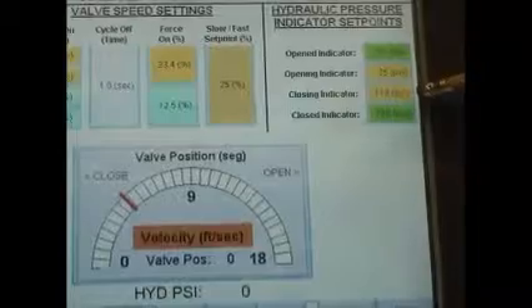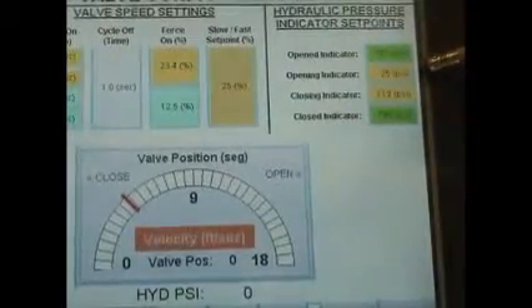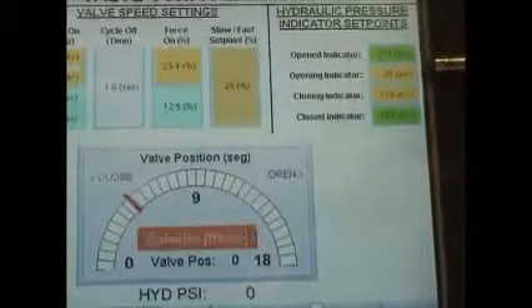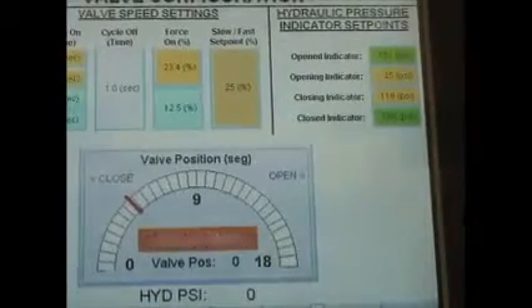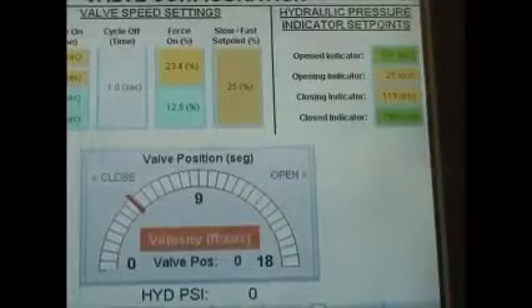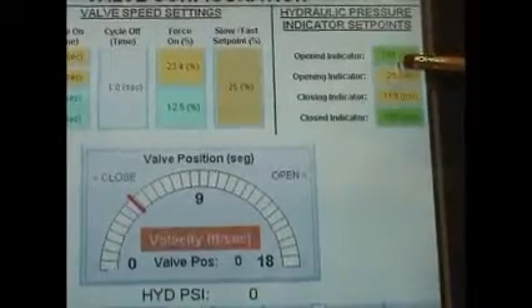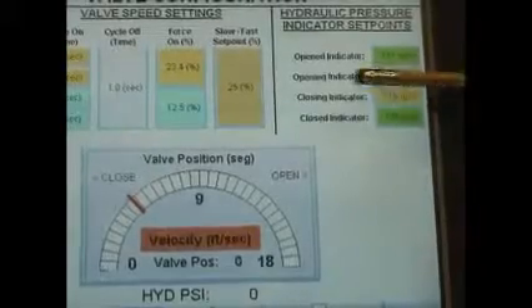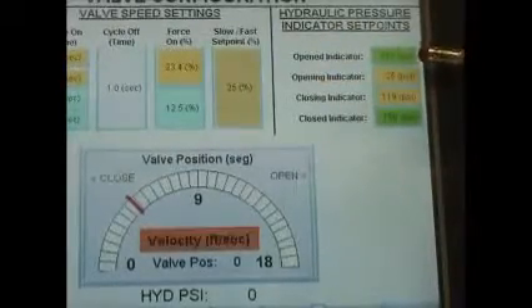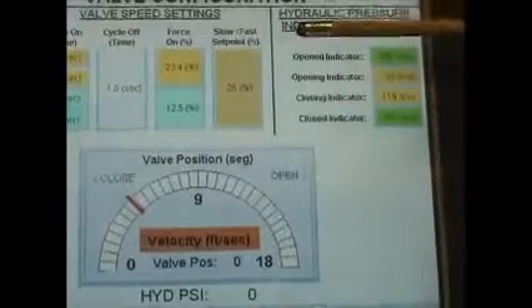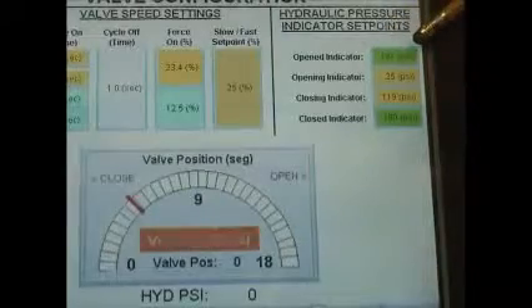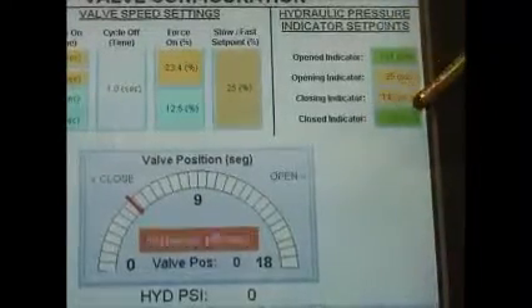The closing set point pressure is usually higher than the opening indicator. The reason again is we have less volume of square inches or square centimeters inside the cylinder going closed than we do going open, so it takes more power or more pressure to close a cylinder due to the decrease in volume of the cylinder going closed than going open. So it is very common to see your open indicator pressure be less than your closing indicator pressure. Your opened indicator pressure and your closed indicator pressure should be pretty close to the same. As you can see, we're at 781 relief pressure on the open side. We're at 780 pounds of pressure when the valve calibrated going closed.